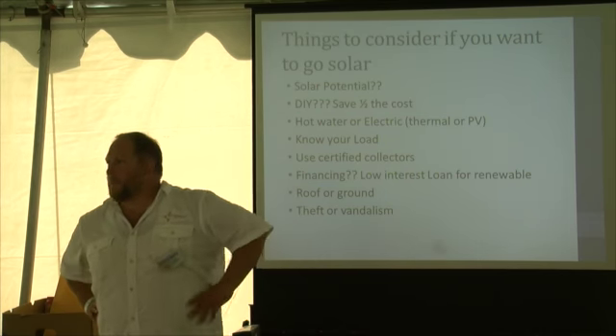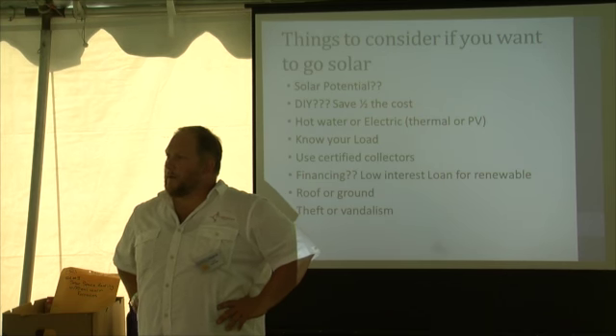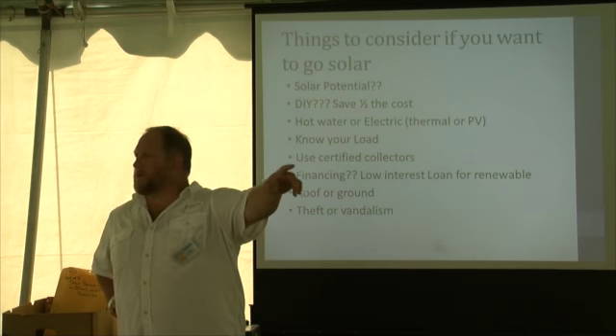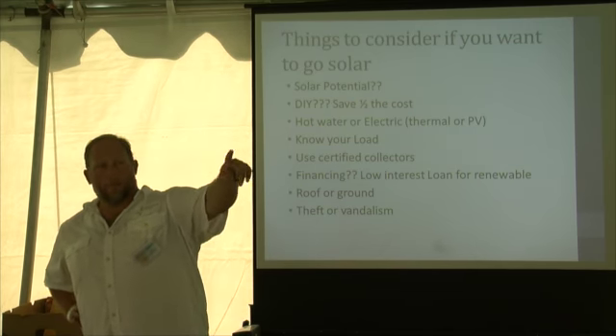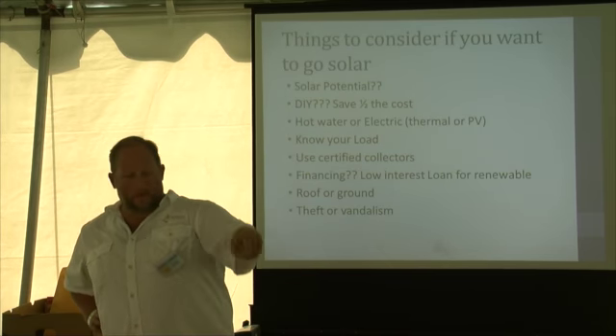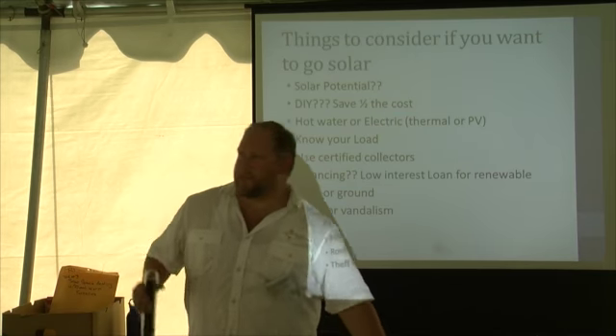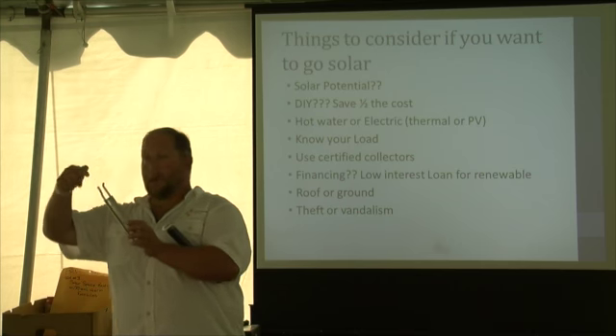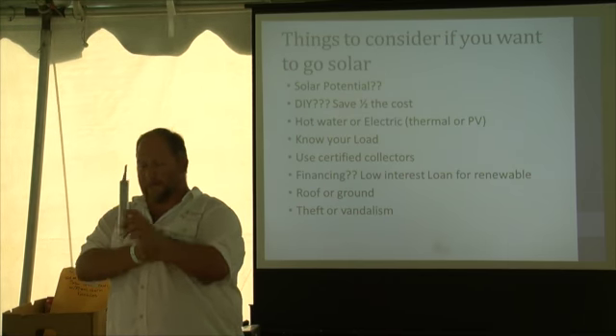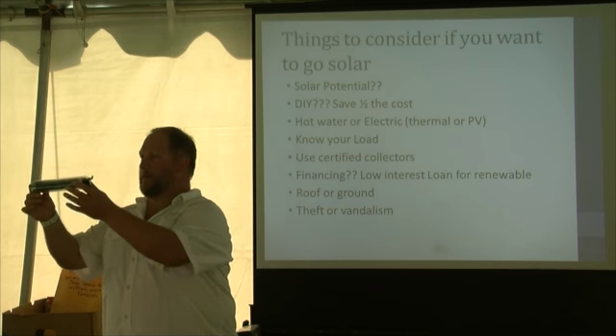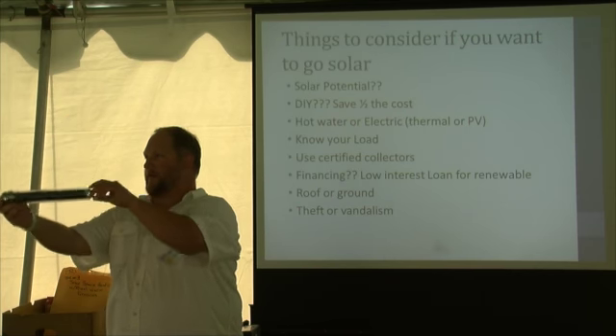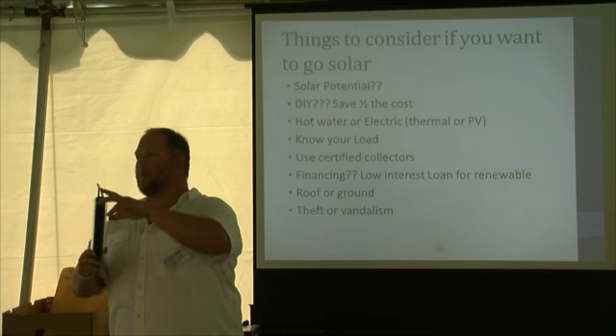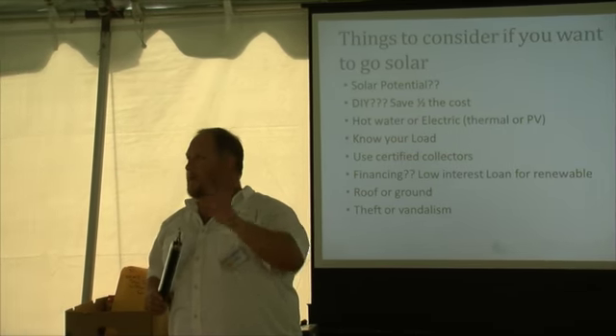Question: can you put the panels with the tubes running horizontally, or do they have to be angled? You can't with the heat pipe tubes. But this style here is a vacuum tube called direct flow, where we're pumping fluid through it. With this style, we can mount it flat like this, because you're pumping the fluid any which way you want. But the heat pipe style, like the big heat pipe collector the gentleman has down here, relies on convection, and it has to be mounted at an angle of at least 15 degrees, no more than 75.